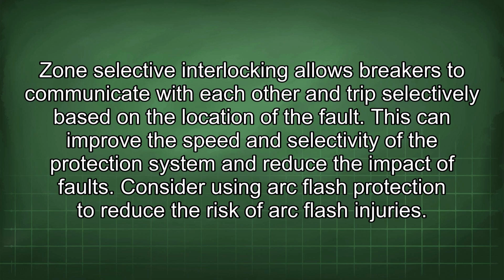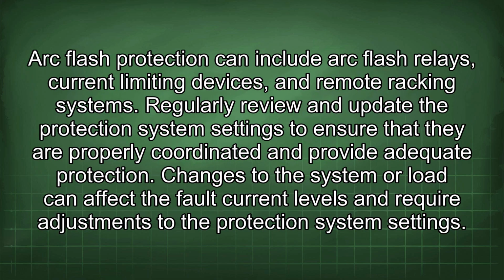Consider using arc flash protection to reduce the risk of arc flash injuries. Arc flash protection can include arc flash relays, current limiting devices, and remote racking systems. Regularly review and update the protection system settings to ensure that they are properly coordinated and provide adequate protection. Changes to the system or load can affect the fault current levels and require adjustments to the protection system settings.